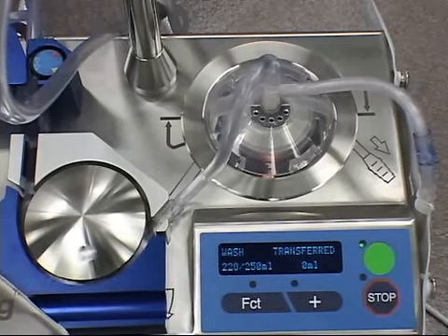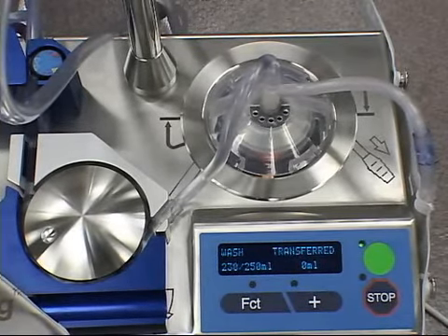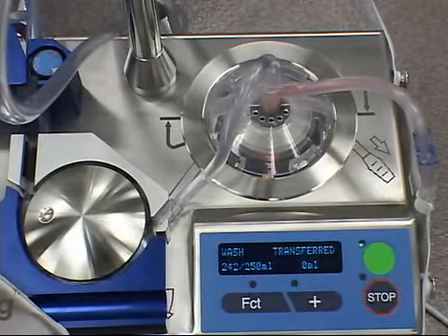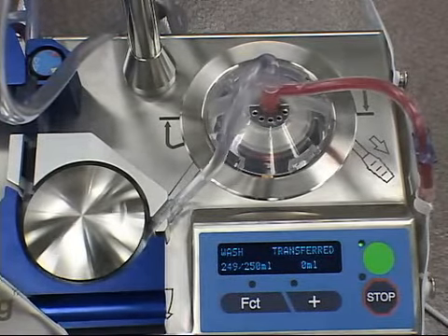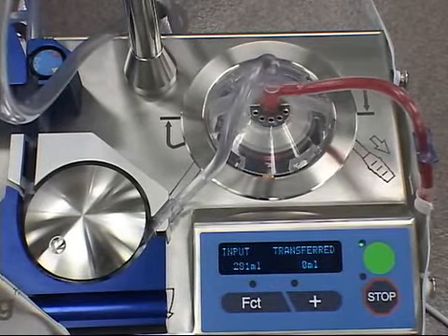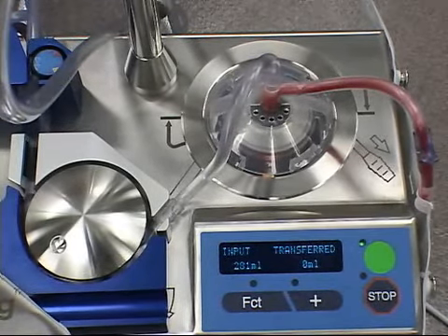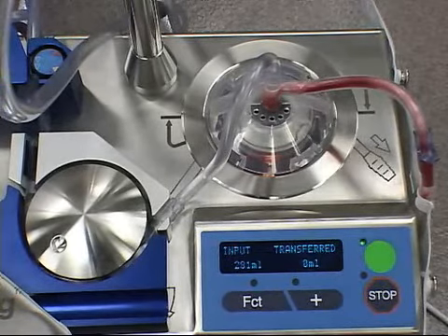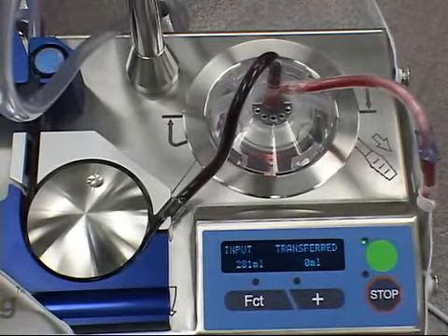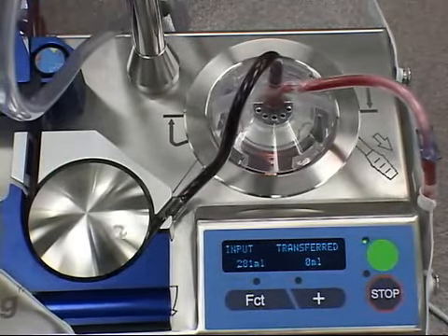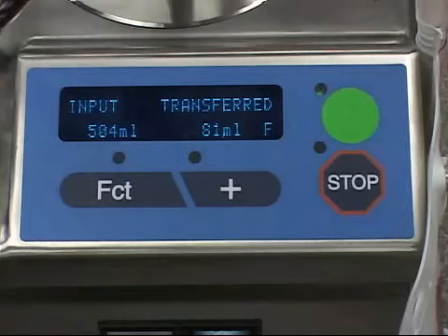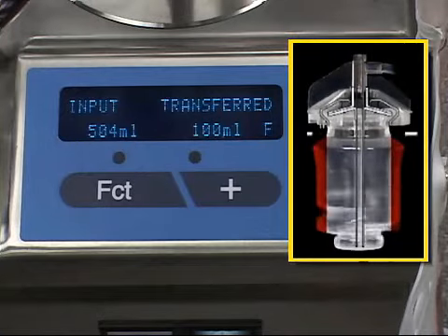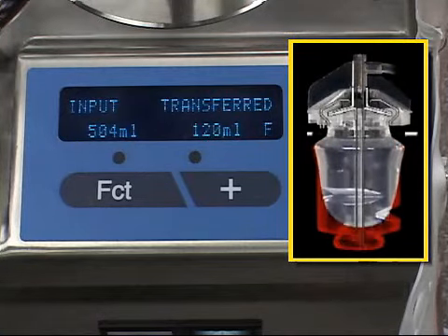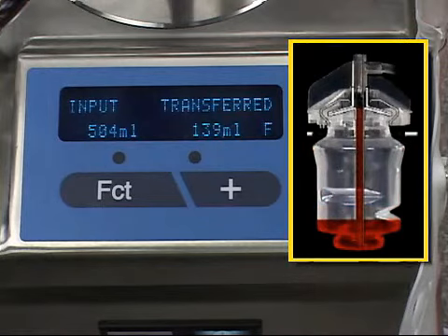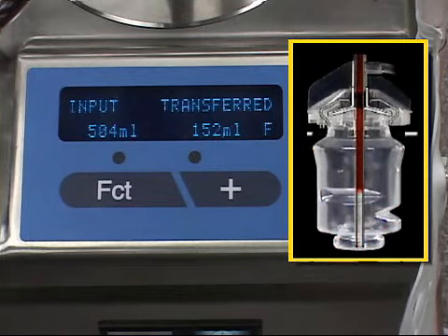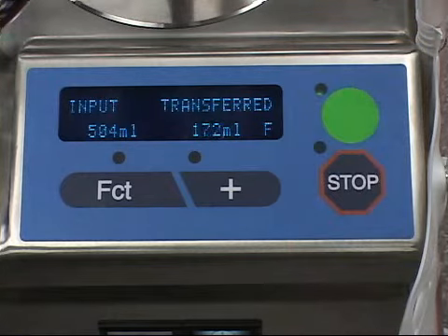The wash phase will start as soon as the level sensor detects a full bowl during the second or final fill. The display shows the volume of wash saline used and total saline volume needed. As soon as the full wash volume of 250 milliliters has been processed and the centrifuge has come to a complete halt, the pump transfers the washed red blood cells to the holding bag. This is the empty phase. The display shows the input volume and the total transferred volume as it is pumping. The first empty cycle will deliver 80 to 90 milliliters of fluid to the holding bag, and approximately 40 milliliters of fluid will remain in the holding bag line.